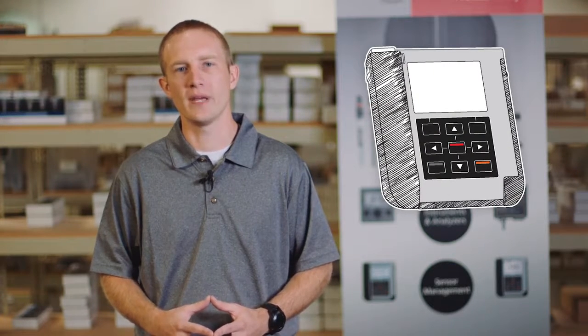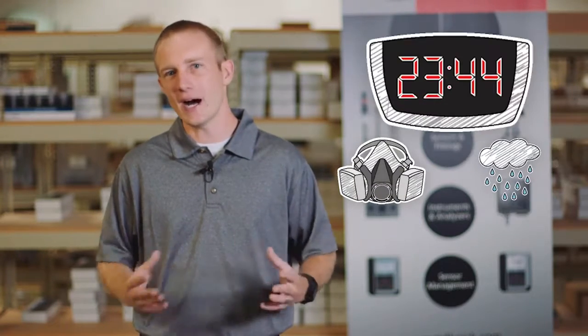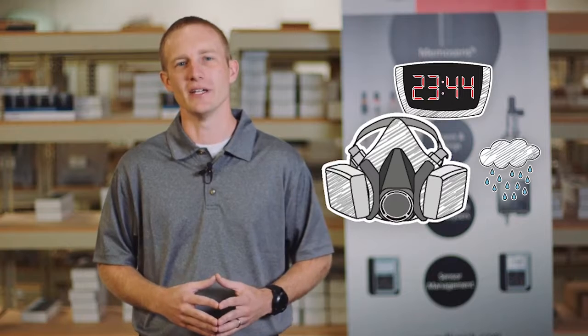Today I'm going to show you how to perform an offline pH calibration using the Portavo 907 multi-portable meter with MemoSense sensors. The primary benefit of using MemoSense digital sensors with a portable meter is that the calibration data is stored within the sensor head and not in the transmitter. This allows us to perform an offline calibration in an environment and at a time that's convenient to the operator. No more calibrating pH sensors in bad weather, at inopportune times, or in hazardous areas.